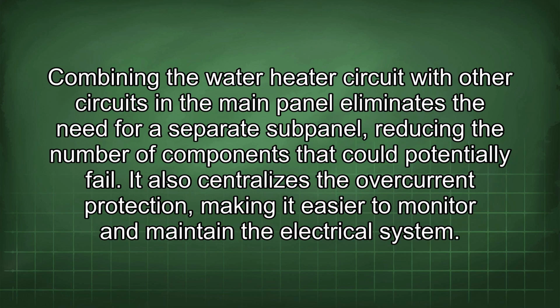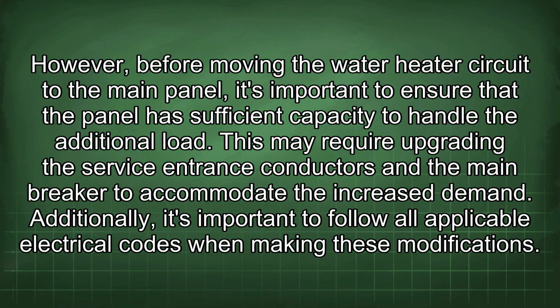Combining the water heater circuit with other circuits in the main panel eliminates the need for a separate subpanel, reducing the number of components that could potentially fail. It also centralizes the overcurrent protection, making it easier to monitor and maintain the electrical system. However, before moving the water heater circuit to the main panel, it's important to ensure that the panel has sufficient capacity to handle the additional load.